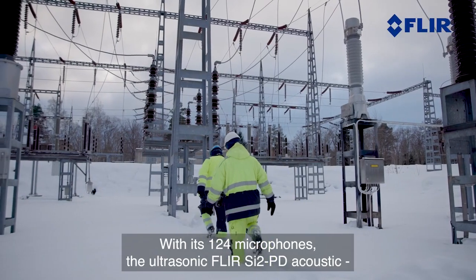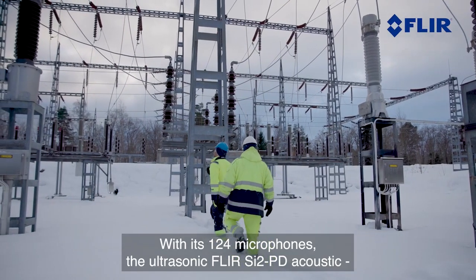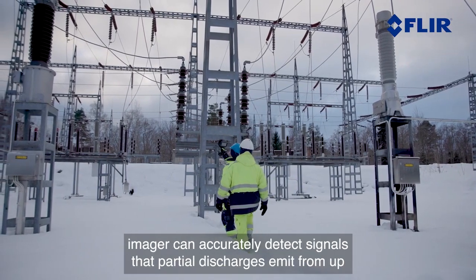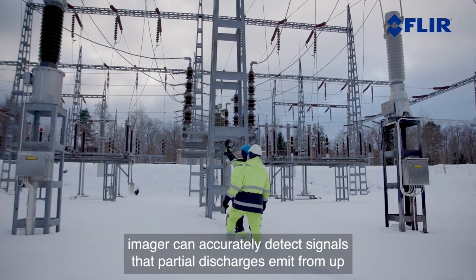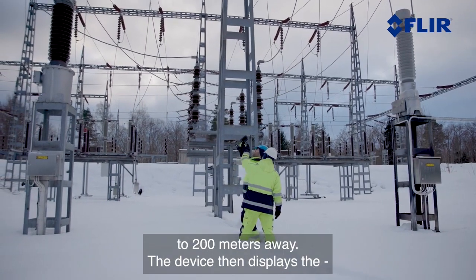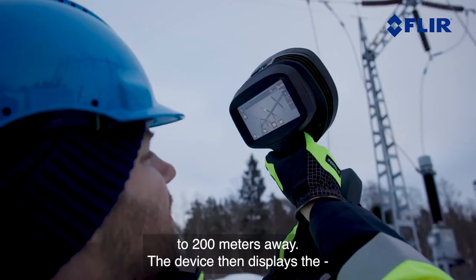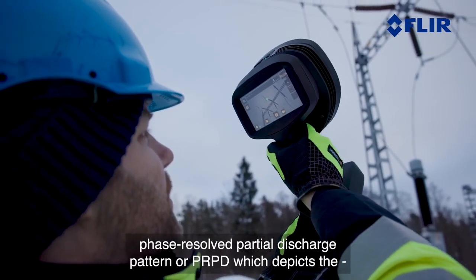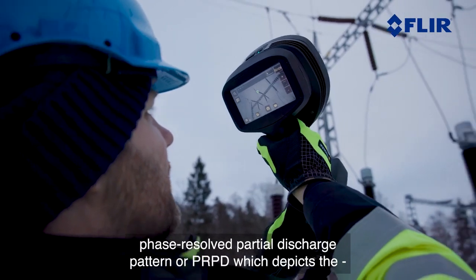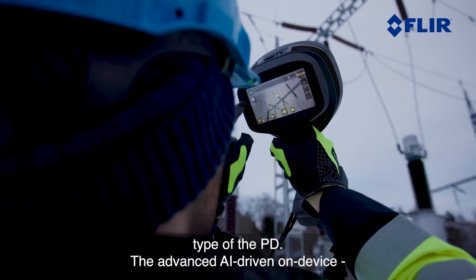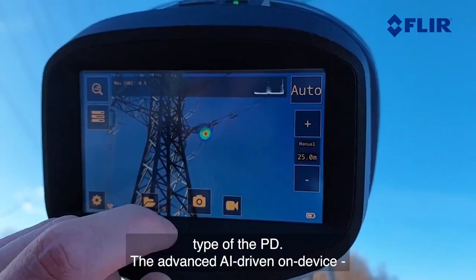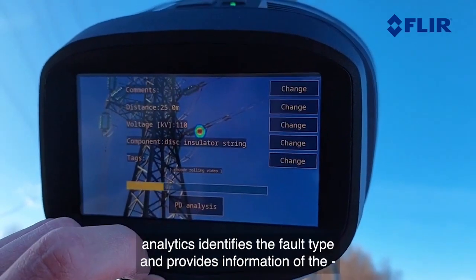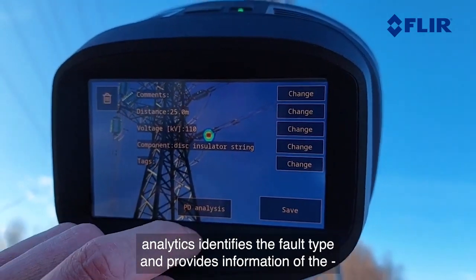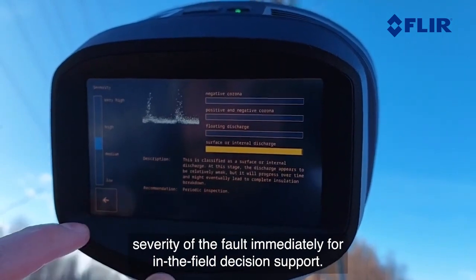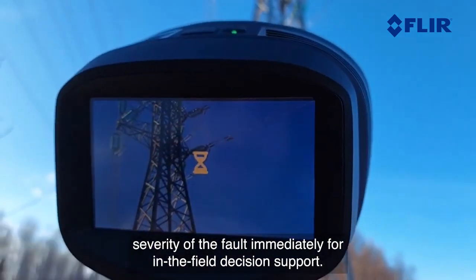With its 124 microphones, the ultrasonic FLIR Si2PD acoustic imager can accurately detect signals that partial discharges emit from up to 200 meters away. The device then displays the phase-resolved partial discharge pattern, or PRPD, which depicts the type of the PD. The advanced AI-driven on-device analytics identifies the fault type and provides information of the severity of the fault immediately for in-the-field decision support.